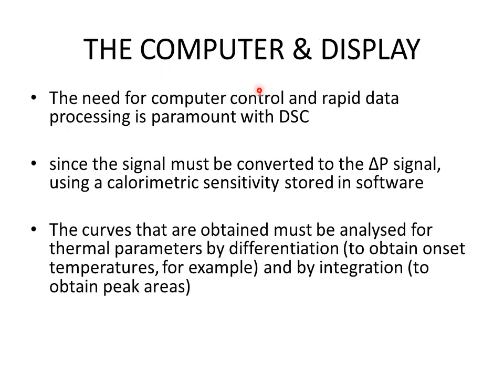Computer control and rapid data processing are essential for DSC. The signal must be converted into a Delta P signal using the calorimetric sensitivity stored in the software. The curves obtained must be analyzed for thermal parameters by differentiation — for example to obtain onset temperatures — and by integration to obtain peak areas. All of these operations are performed automatically by the system software.